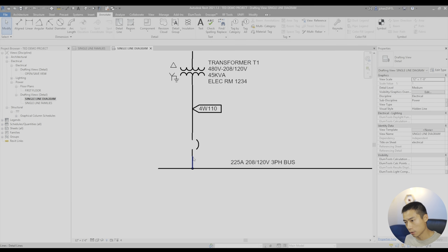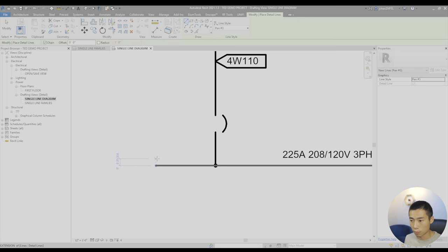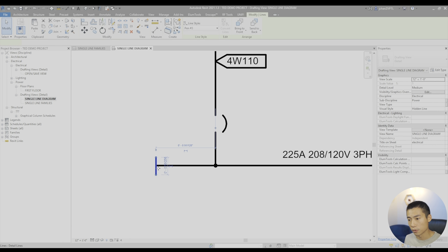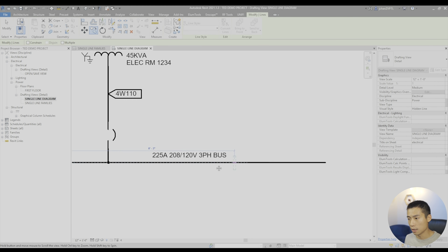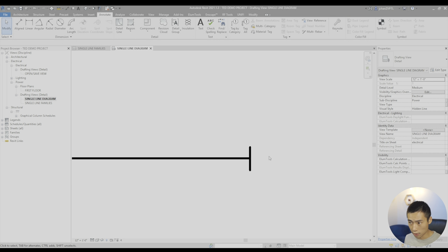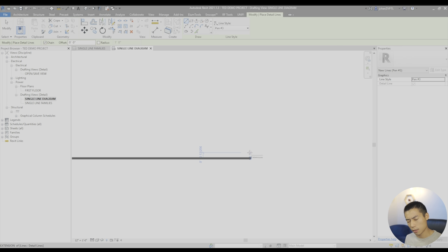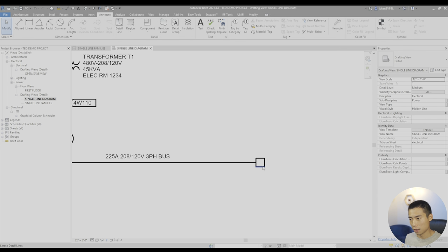So that shows that you're connecting to the bus here. You also want to show your termination of the bus. So this is a termination, and if you wanted expansion feed through lugs at the end, you can do a box, and then you'll have to call that out by a note. So this signifies that it can be expanded in the future just by continuing the bus in another panel.